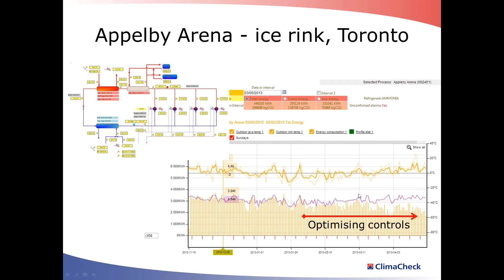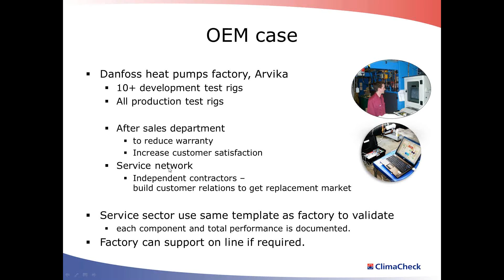We also supply quite a few manufacturers using it in their development test rigs and production test rigs, and also for after sales. It's very expensive for manufacturers to have problems in the field when the contractor and end user are not satisfied with the product. If you have access to the ClimaCheck information, you have the same information as in a test rig in a factory, so it's very easy to pinpoint problems and know if it's internal in the system or outside of the unit.